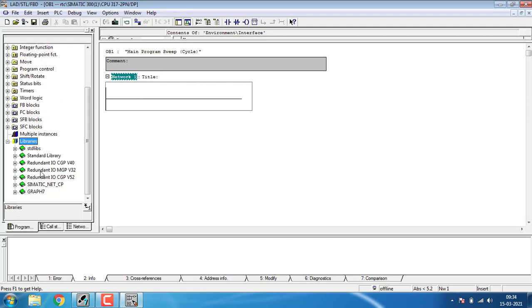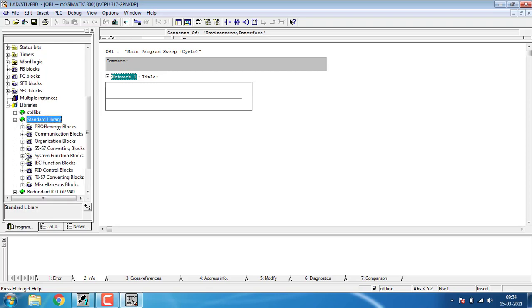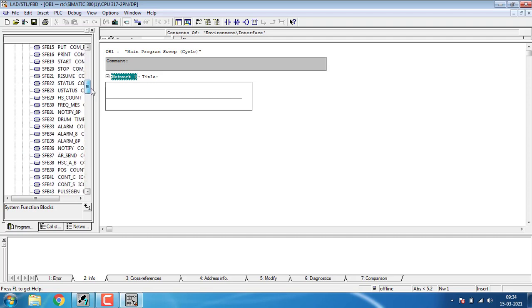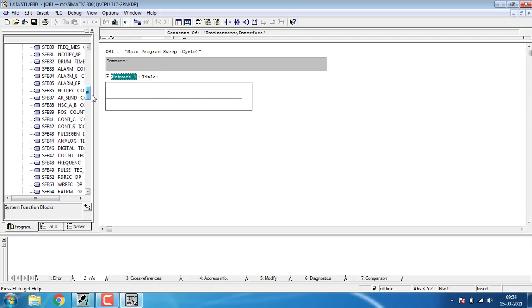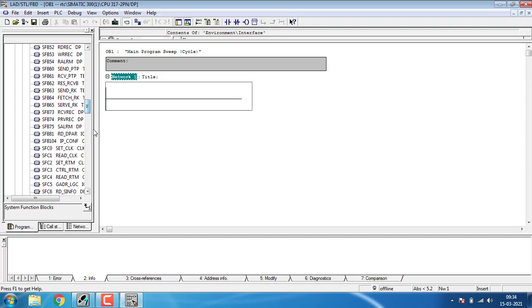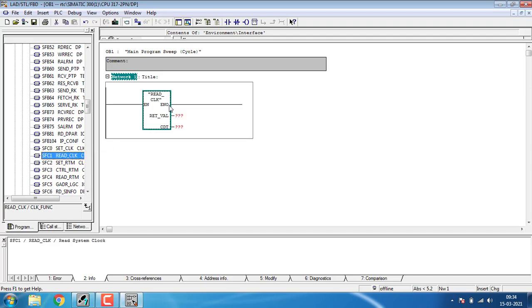For setting up the real-time clock, go to the libraries. Inside the library you can see the standard library. Inside the standard library, I'm going to the system function blocks. In the system function blocks, we have to go for the real-time clock adjustments. SFC 1 is the read clock function, SFC 0 is the system function for real-time clock adjustment. You have to read the clock value for setting it.